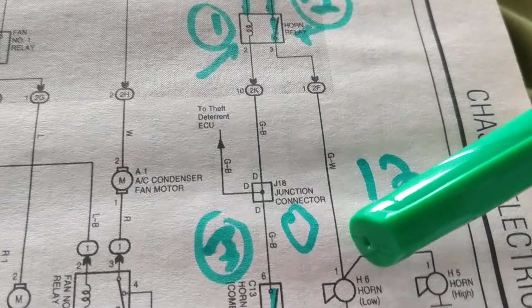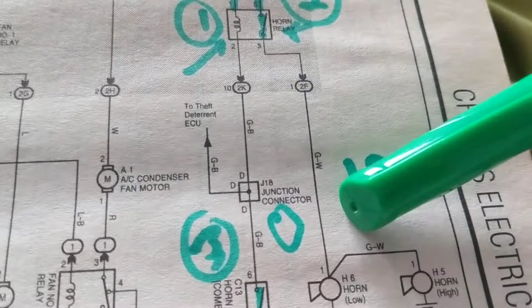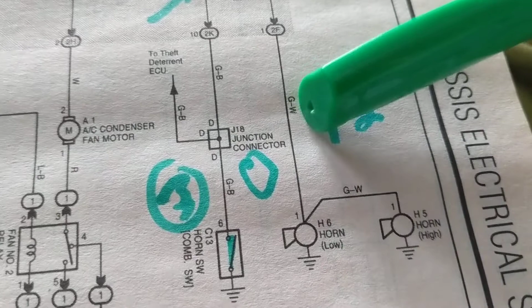I come down here and I say, okay, where am I going to measure? Am I going to go to the connector of the horns? And I measure 0 volts, 0 volts over here. That tells me either I'm shorted to ground. It could be that this wire is going to ground. The green and white wire is going to ground.